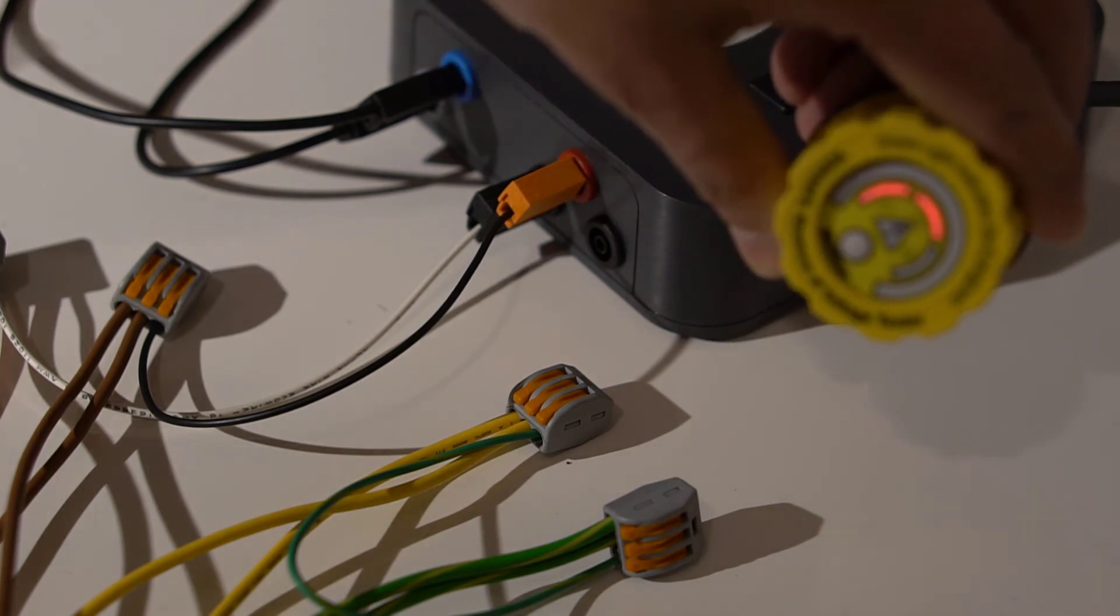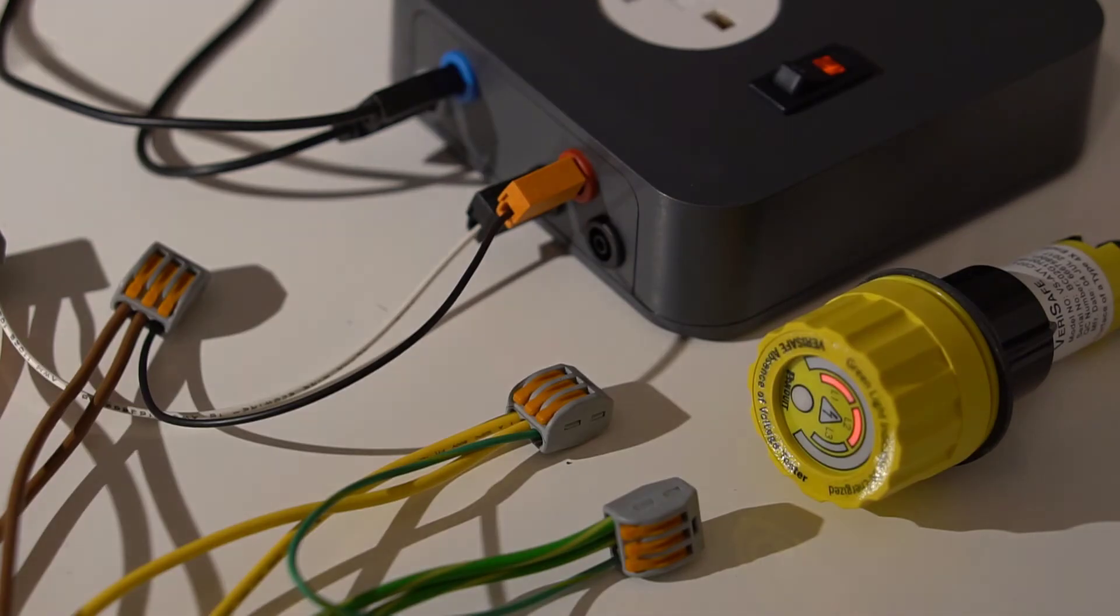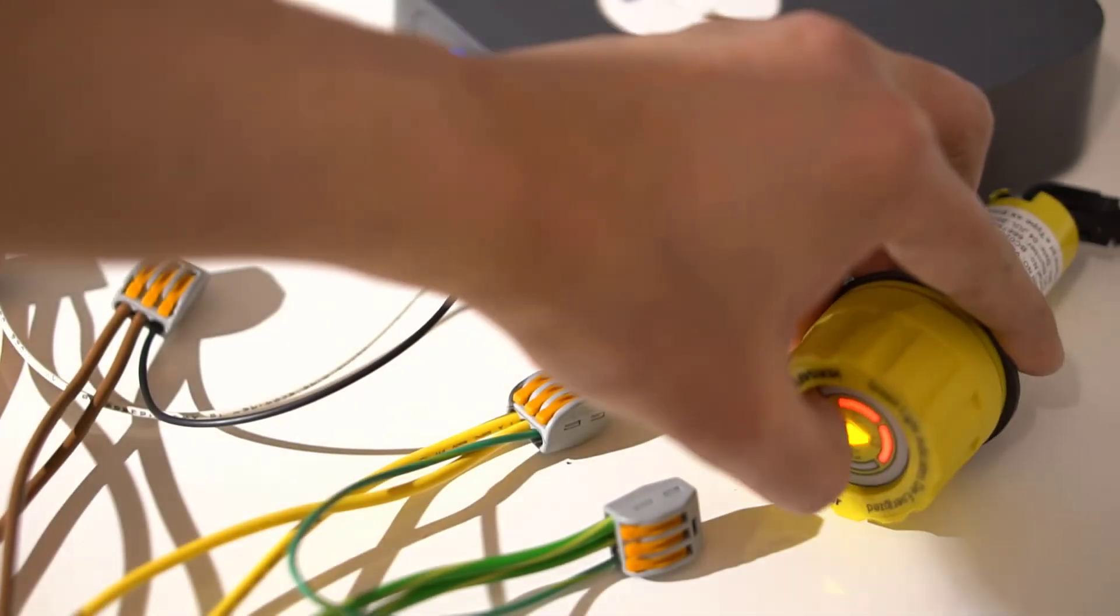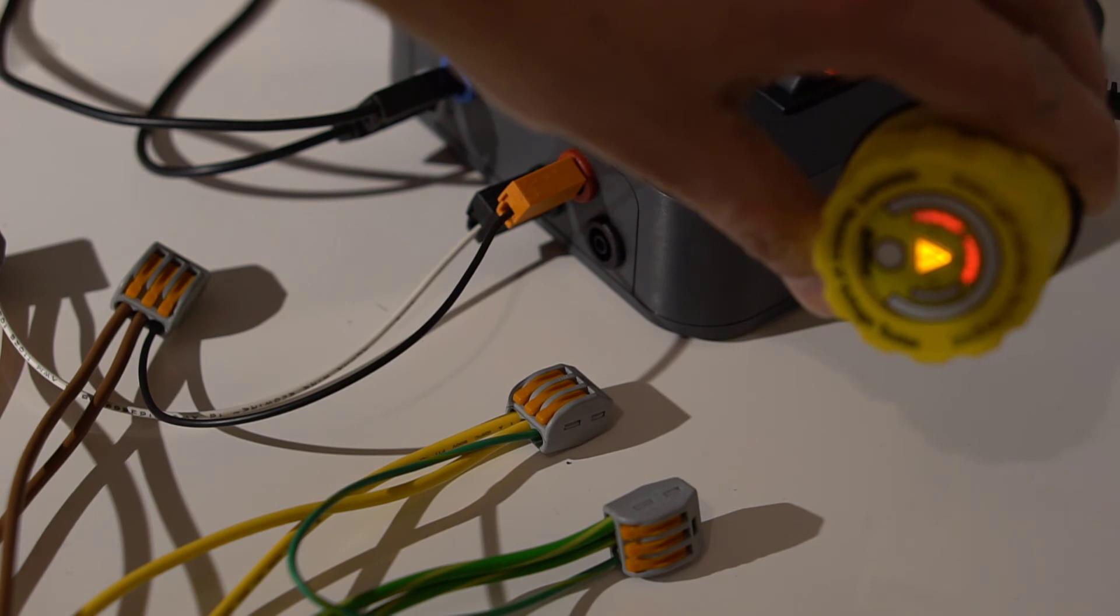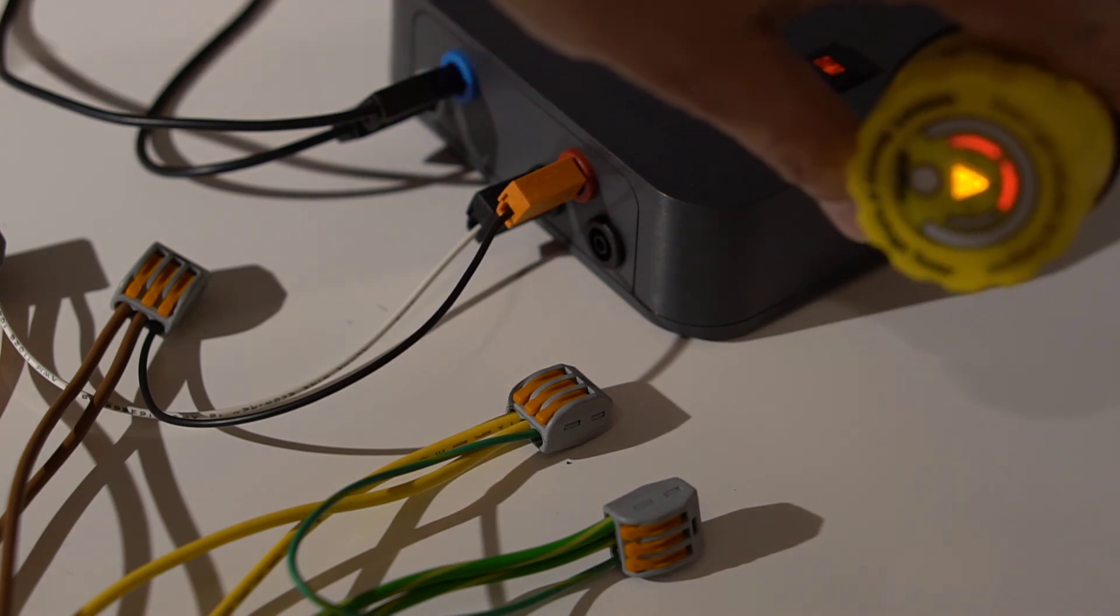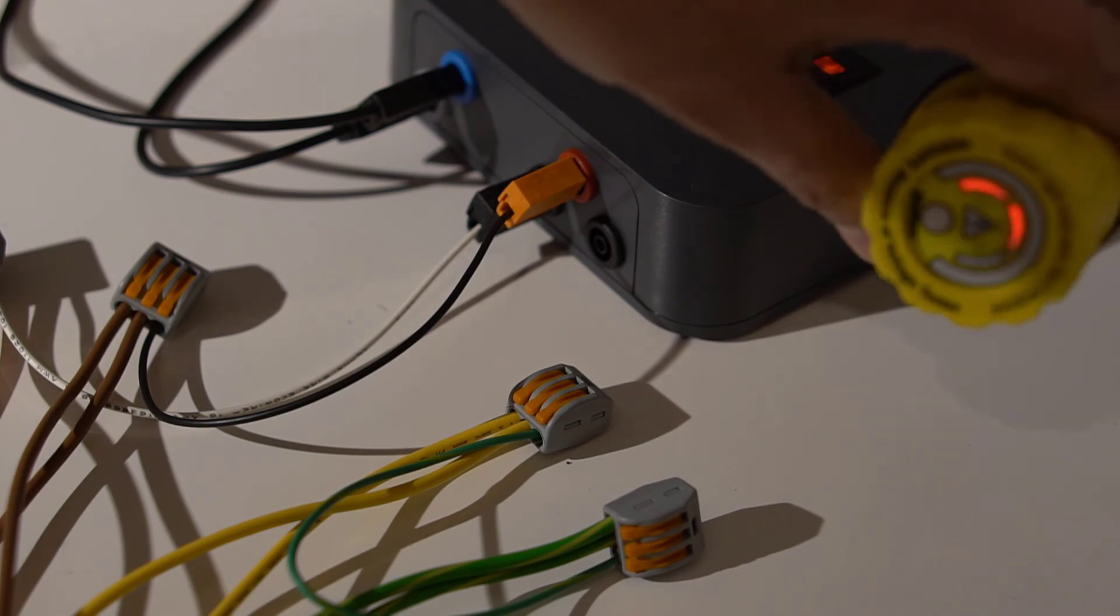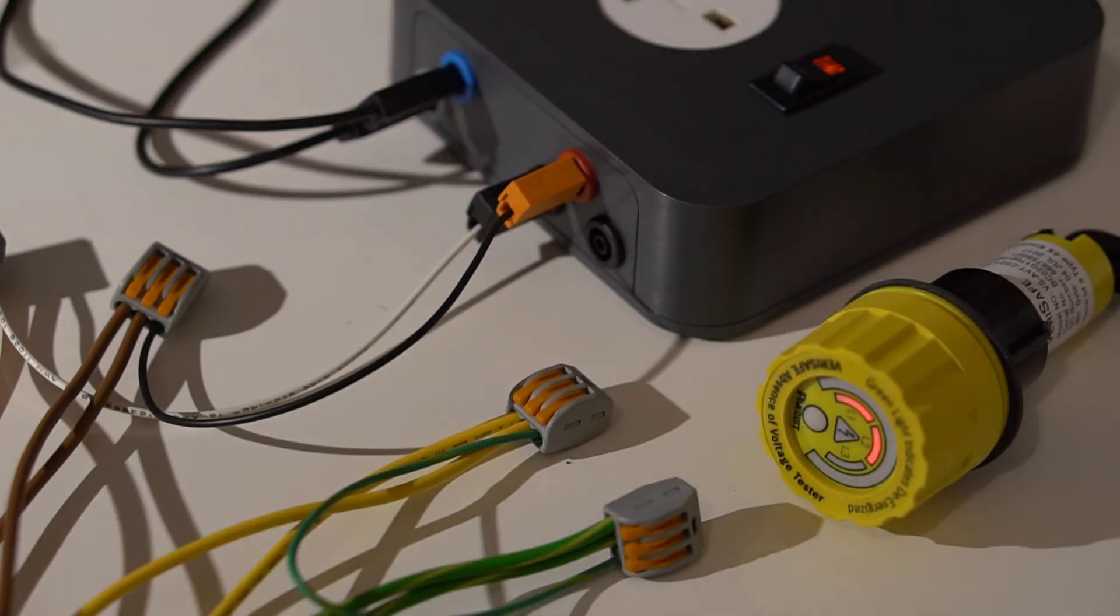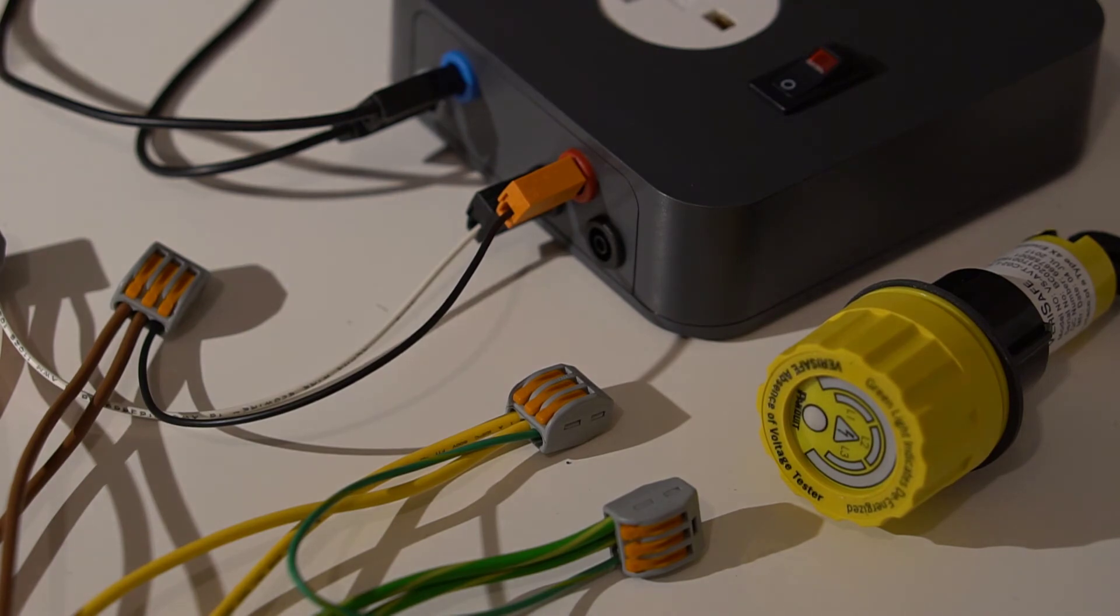The absence of red does not necessarily mean that there is no voltage. The only safe condition is when the green light comes on. Now if I press the test button I'll see two flashes to indicate that the voltage has been detected, and that power needs to be removed for everything to be safe. If I switch the power off, then all is good, and the green indication comes on.